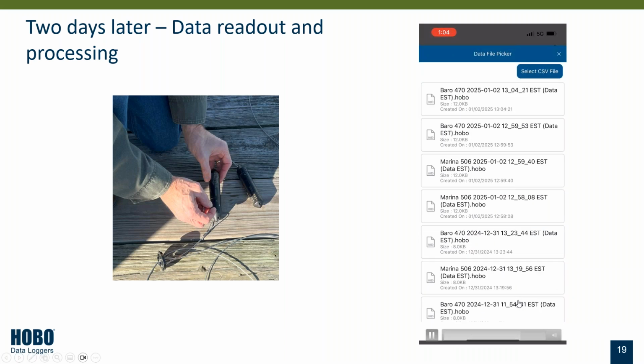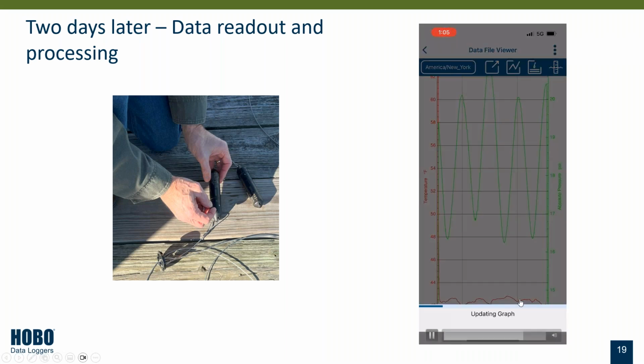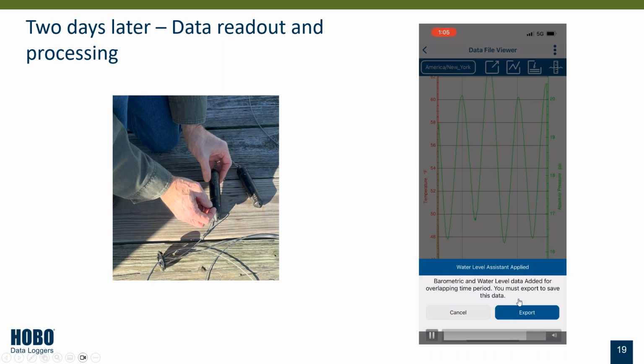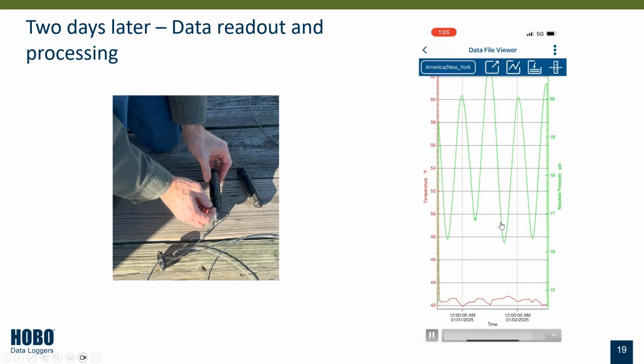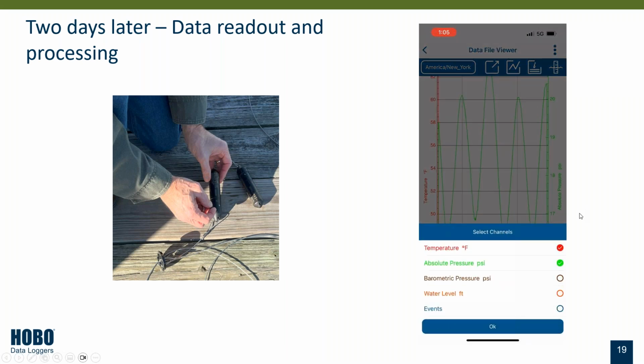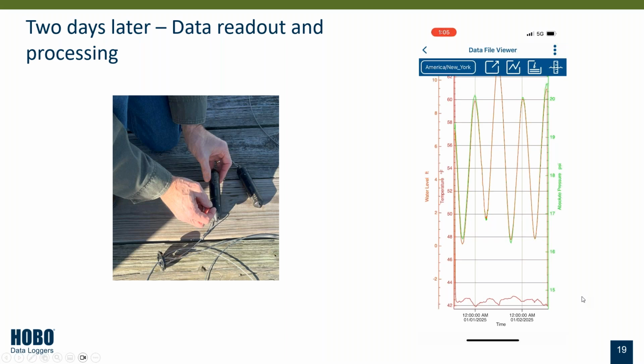The next thing I want to do is select my barometric pressure data file. Done, and it's now calculated the water level data. Next I want to click on this thing that looks like a graph up here to select the water level channel. I selected the water level channel, and now that's been added to my graph. It's pretty close in this case to the absolute pressure data, so you can see the two plots tied pretty closely together.